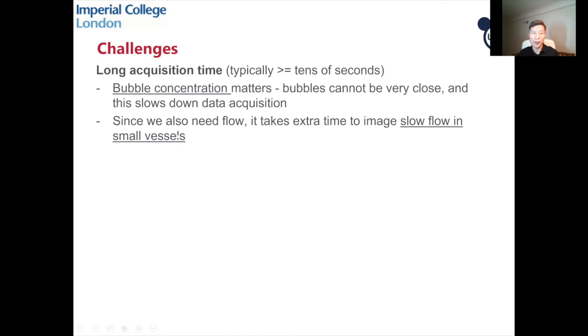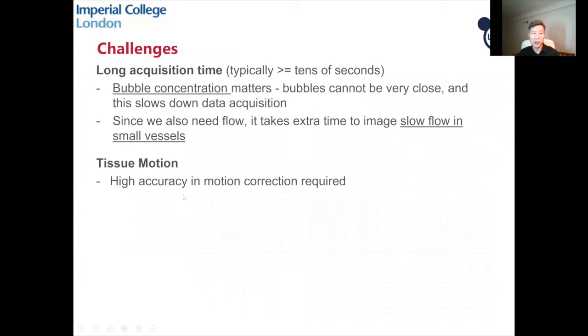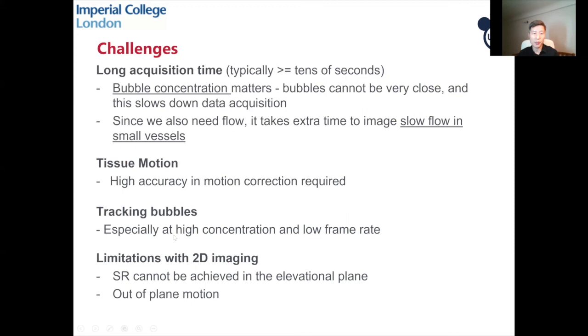Since we need flow, it takes extra time to image slow flow in small vessels because you have to wait until the small vessels are perfused with these agents. Another challenge is tissue motion — tissue always moves, especially over long acquisition times. To correct this motion, when we're talking about spatial resolution at the level of tens of microns, tissue motion correction accuracy must be at least at that level. Another challenge is tracking bubbles, particularly when bubble concentration is high and frame rate is low.